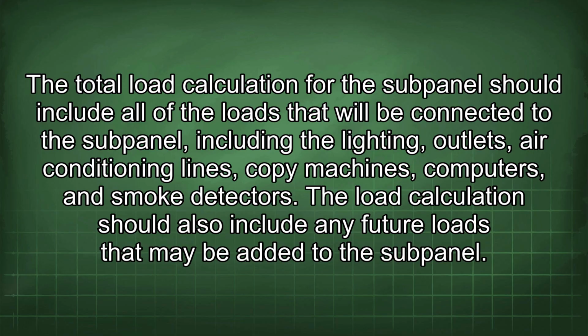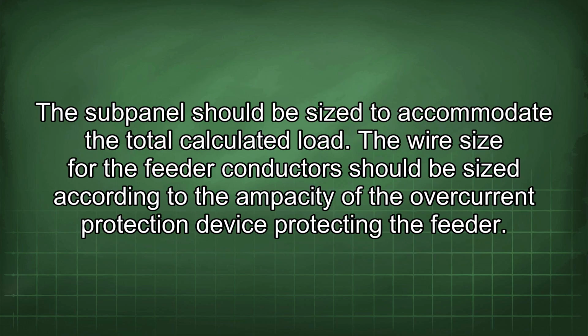The total load calculation for the subpanel should include all of the loads that will be connected to the subpanel, including the lighting, outlets, air conditioning lines, copy machines, computers, and smoke detectors. The load calculation should also include any future loads that may be added to the subpanel. The subpanel should be sized to accommodate the total calculated load.